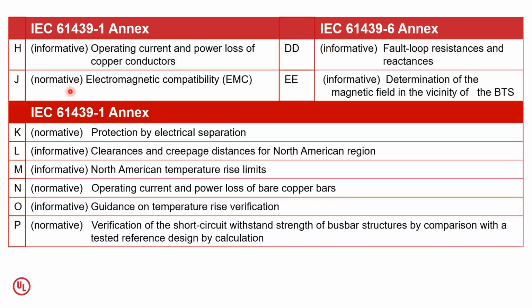The reason it is made normative is that if your busways have any sort of electronic component, for example an electronic molded case circuit breaker, then that particular molded case circuit breaker should have already complied with EMC, or there would be a requirement for EMC testing, without which you can't claim compliance to the 61439 series. Similarly, when you go to the Part 6 standard, you again have informative requirements. One is the fault loop resistance and reactance, and then you have the magnetic field determination.